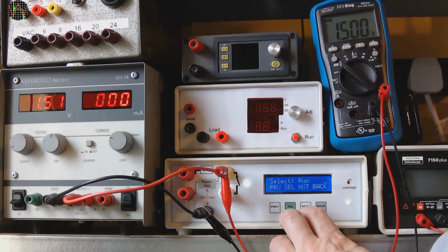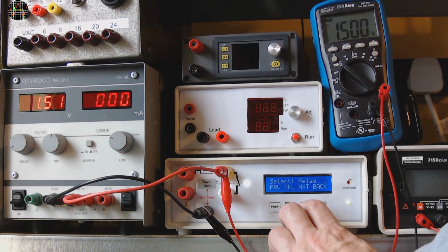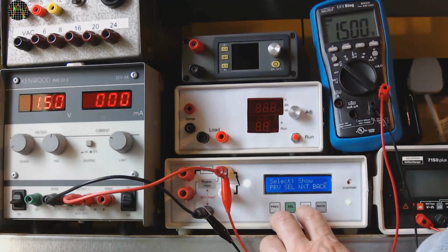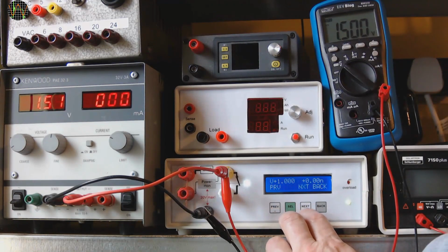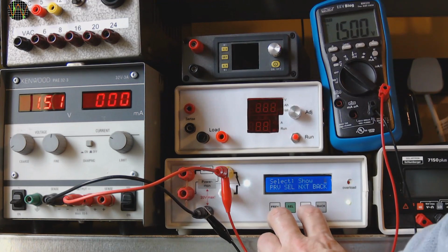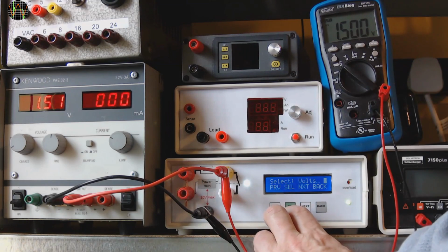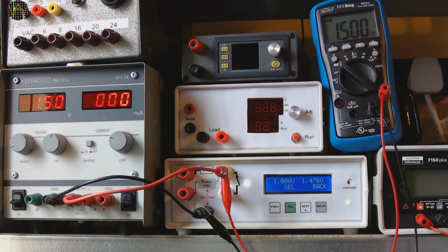Once you enter the new calibration menu from the main menu, you can use Show to see 5 slope and intercept values, one set for bus volts with V in the left corner, and 4 for the current ranges A to D as determined by the current shunt value. You can select volt or each of the 4 current ranges. For example, I select volt. The program turns off any existing calibration temporarily and shows a target, here 1 volt on the left and the actual reading on the right.